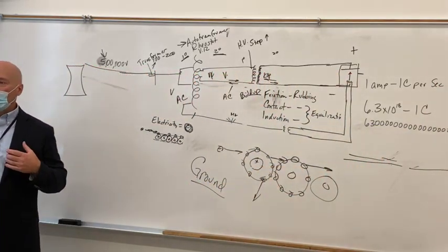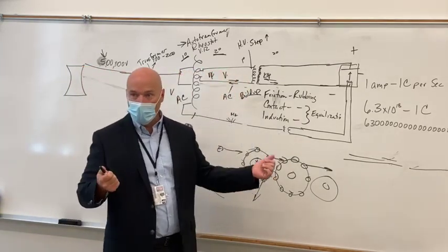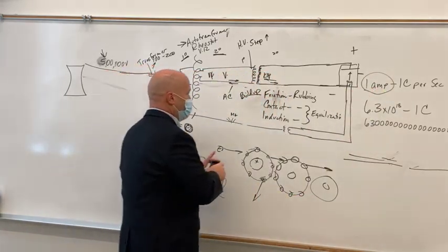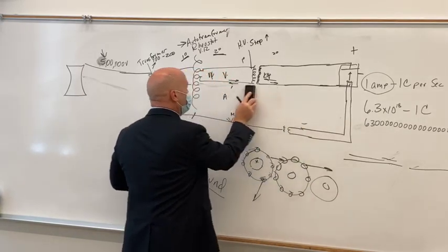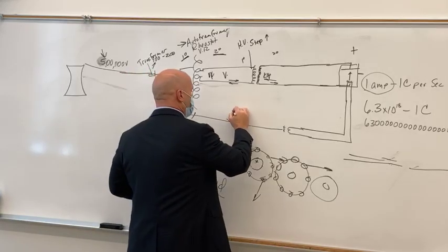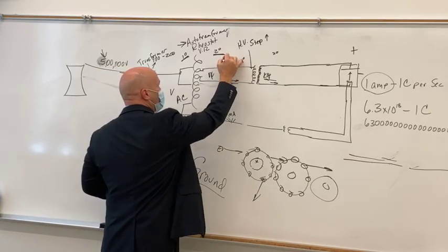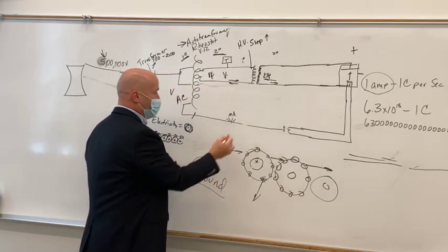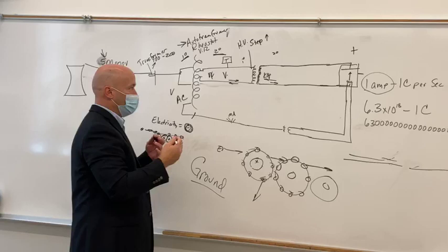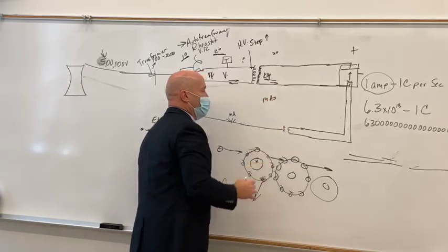All right, so our units of radiation exposure, we have kVp and we've got amperage, right? So that's what we're talking about in amperage. So I said we were gonna get back to this, and we are. So when you set your MA, what you're setting is this circuit here. You've got some other circuits up here. You've got a timer circuit, so that when you make an actual exposure, you can measure the MA that you created and the time that you created the MA, so that you get your overall mAs, right?